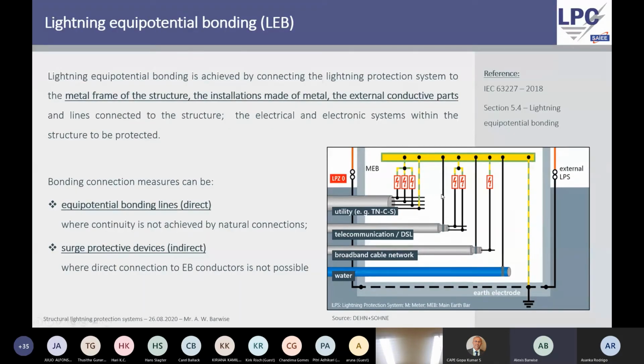And this is best explained by the graph on the right here. In a house you would have a main earth bar. You might have the external lightning protection system all interconnected via, in this case, the type B earthing system. It goes back electrically to the earth bar, and you would connect the earth cables to the earth bar. You would connect the shields of telecommunication cables to the earth bar, but you could not physically connect the live wires of your power system or the transmit and receive wires of your telecommunication system to earth. And this is where we are using suitable surge protection devices, because during the condition where there is a huge potential exerted onto the earth bar, we need to ensure that these potentials are equal such that we don't have damages. This is when the surge protection device switches on and creates an equal potential, then via bonding, such that the equipment connected to the power line or the telecommunication lines is not damaged.